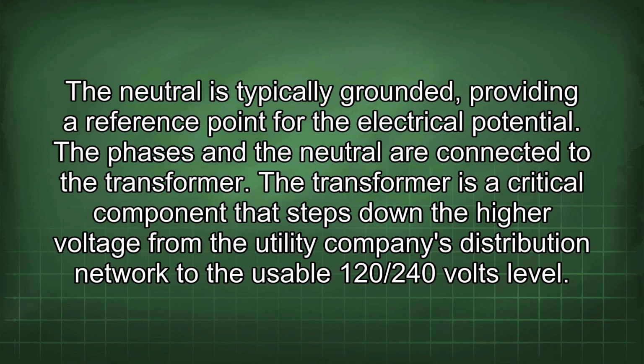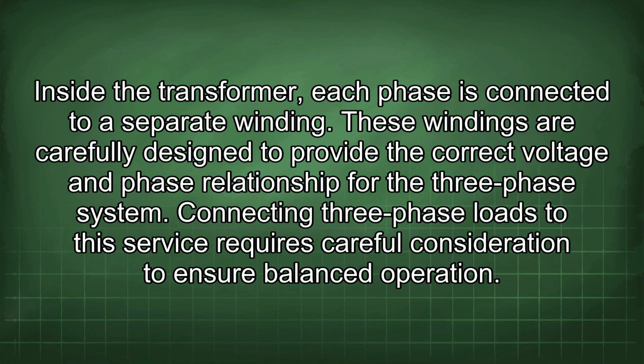The phases and the neutral are connected to the transformer. The transformer is a critical component that steps down the higher voltage from the utility company's distribution network to the usable 120/240 volts level. Inside the transformer, each phase is connected to a separate winding. These windings are carefully designed to provide the correct voltage and phase relationship for the 3-phase system.